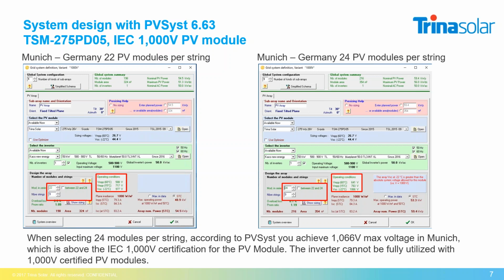and I exceed the certified maximum system voltage, which means I need to reduce the string length, or if I go with the longer string, I may have trouble if something happens. For example, if people have to do maintenance during the winter time, there's a risk of an electrical shock, because, for example, the inverters are offline, or if the inverters have something wrong or are taken off the grid, you always have the system running in VOC conditions. That means if something happens, you need to make sure that you're within the certifications.